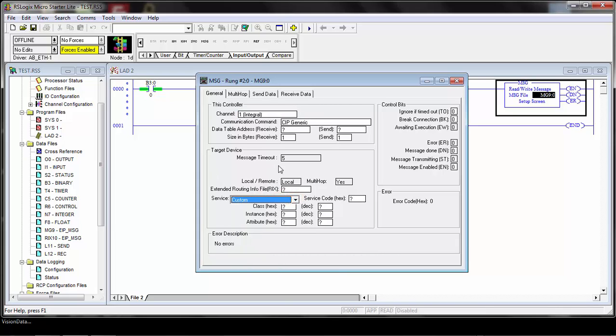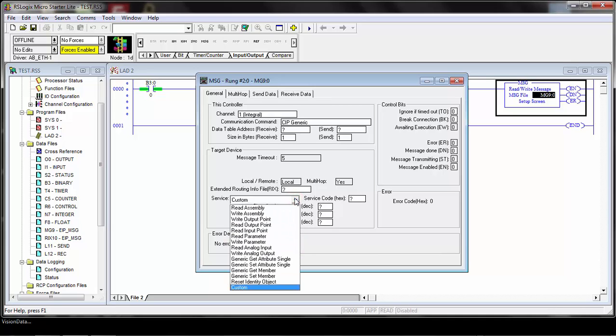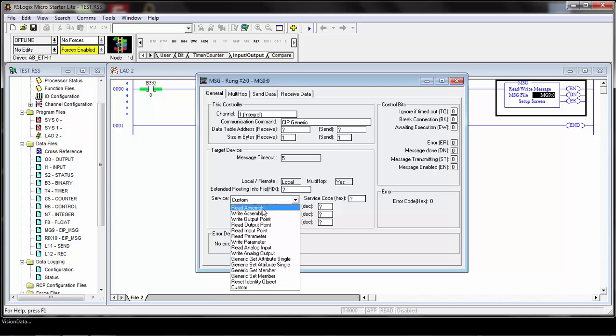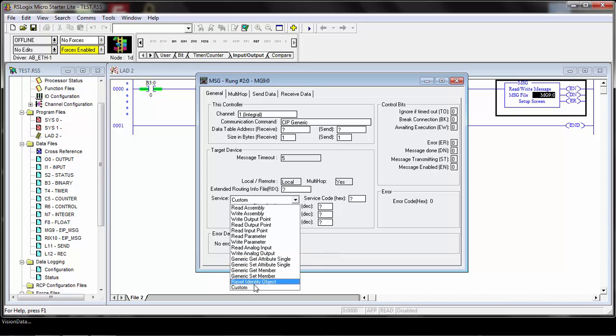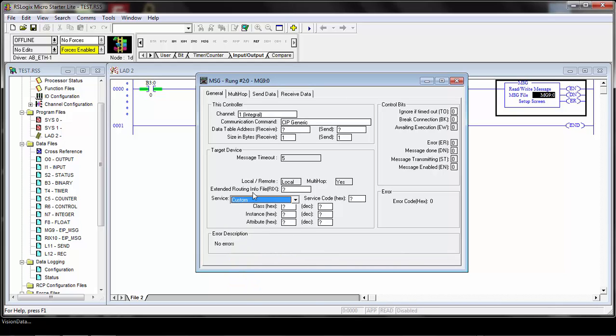There's a couple of different things you can do with Ethernet IP explicit messaging, like read the assembly and write the assemblies. That's reading and writing the entire data assembly, similar to what ControlLogix does automatically through the implicit type communication. You can even get and set single attributes, but the most common thing you can do is what's called a custom service. We're going to choose custom as the service and set up the rest as we go.